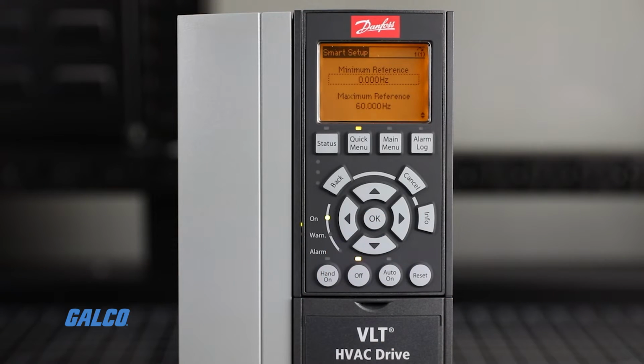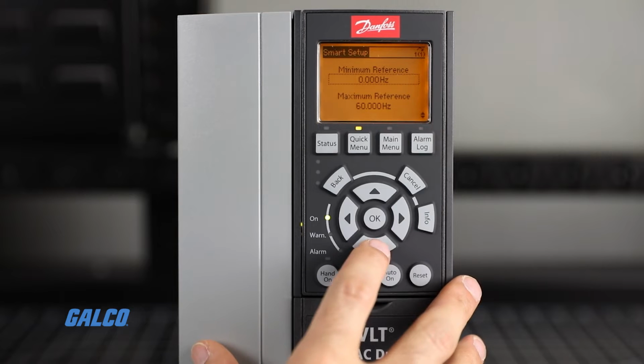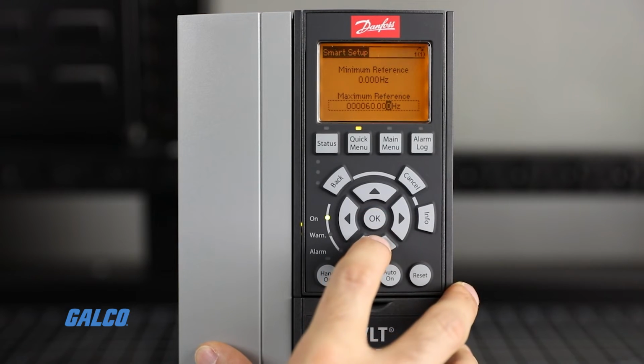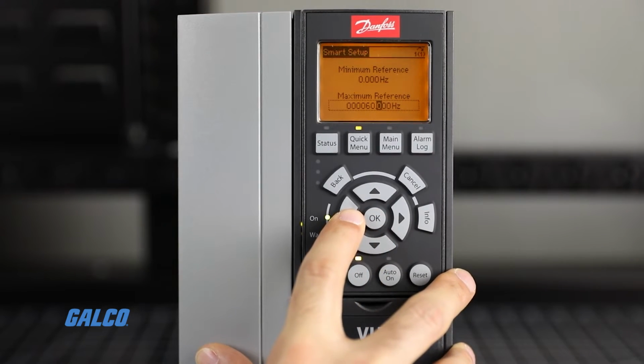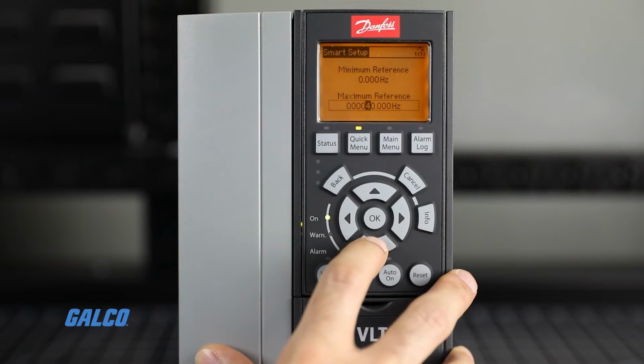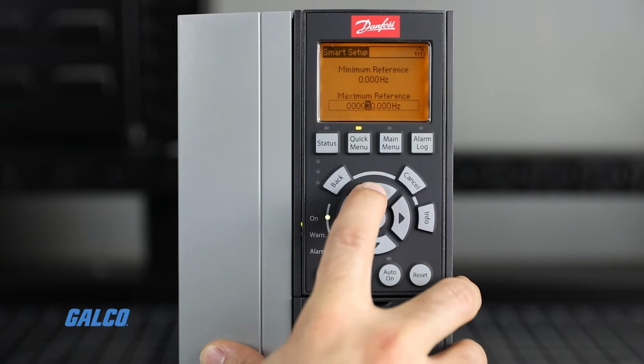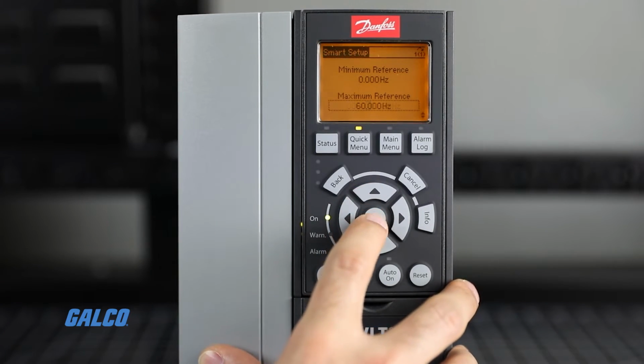Move on to parameter 3-02 minimum reference, which programs the minimum speed reference. You can leave this value at 0 RPM. Parameter 3-03 maximum reference programs the maximum speed. Set this value to 1800 RPM, which is equivalent to 60 Hz frequency on a four-pole motor.